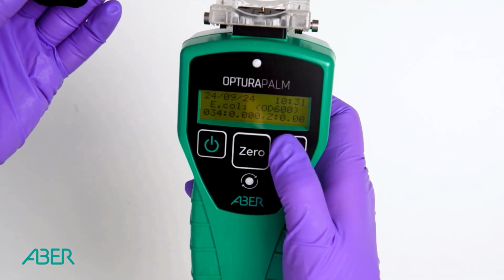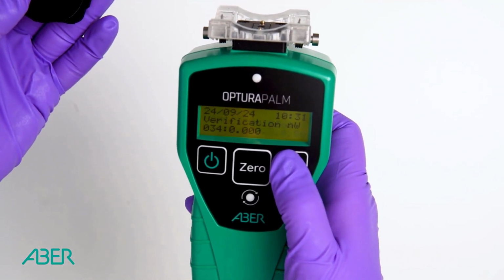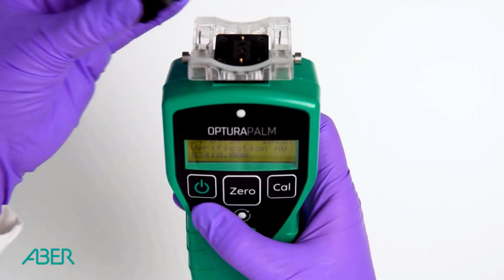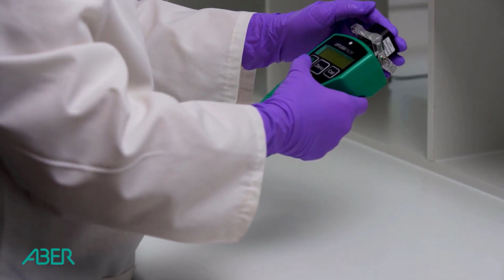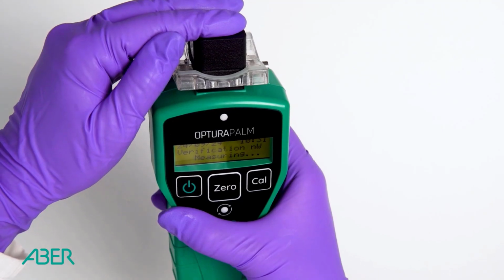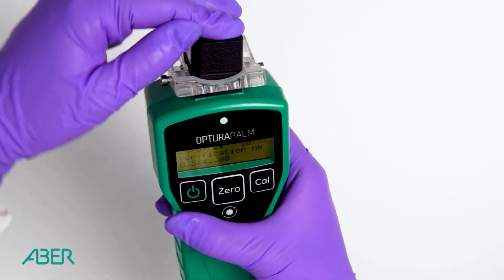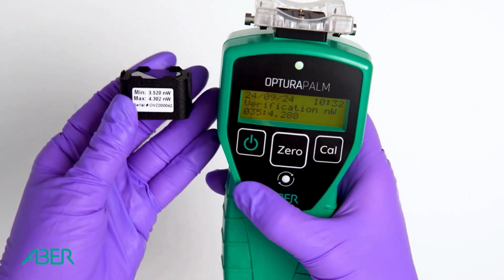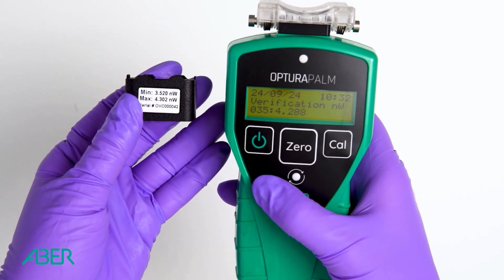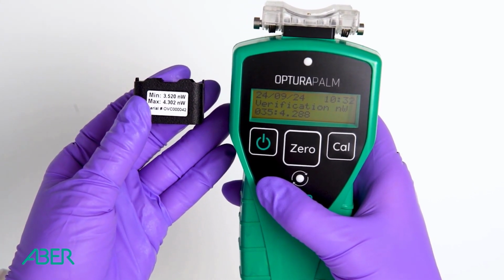To take a verification reading, cycle through the Cal button to find Verification Nanowatt. Hold the block against the measurement face, engage the pins by pressing firmly, and you will hear the tones along with the screen prompt which indicates the measurement is in progress. Your measurement should lie between the min and max tolerances printed here.